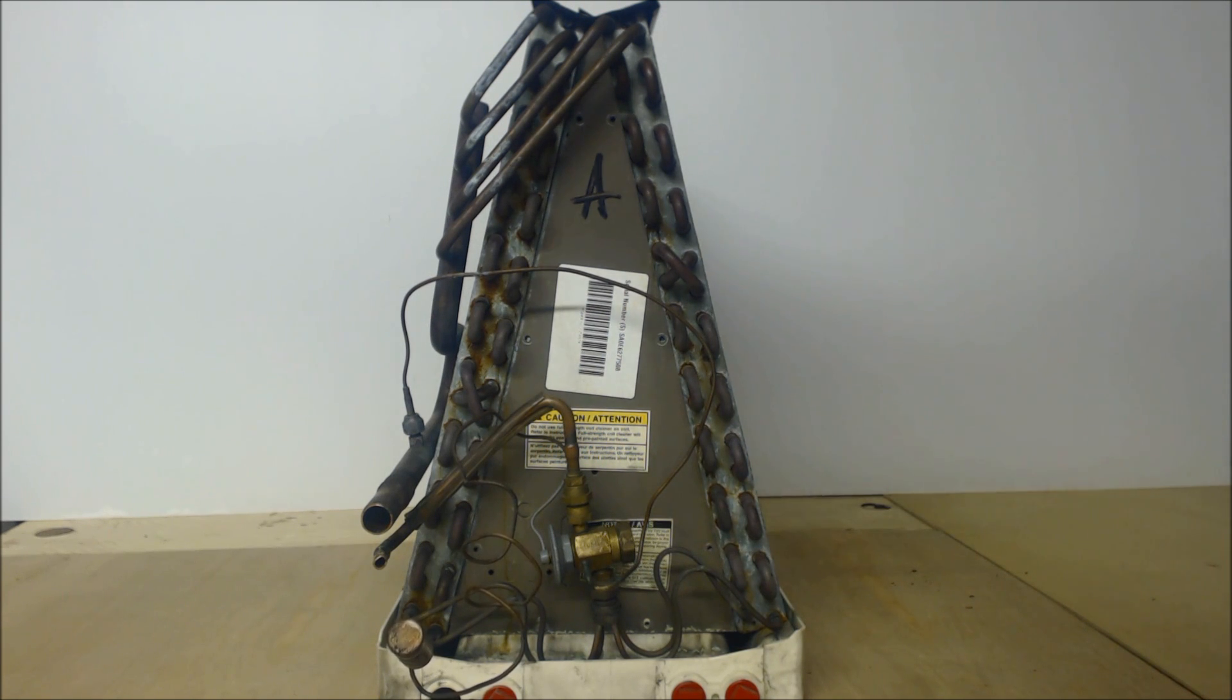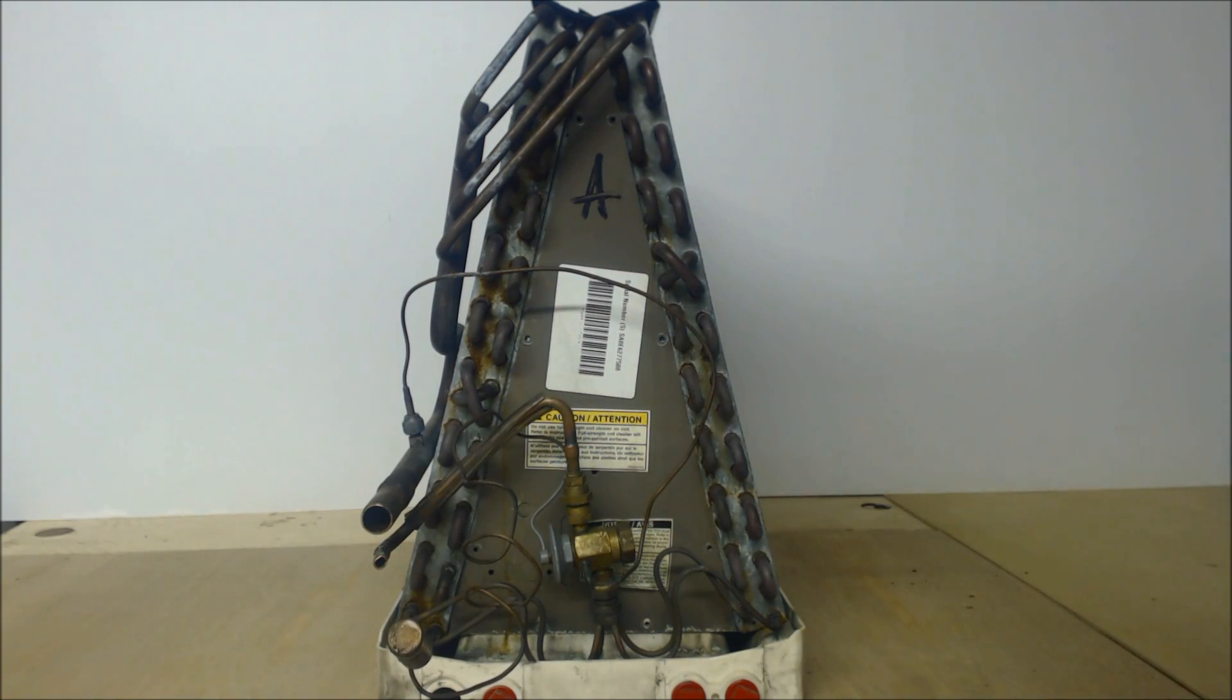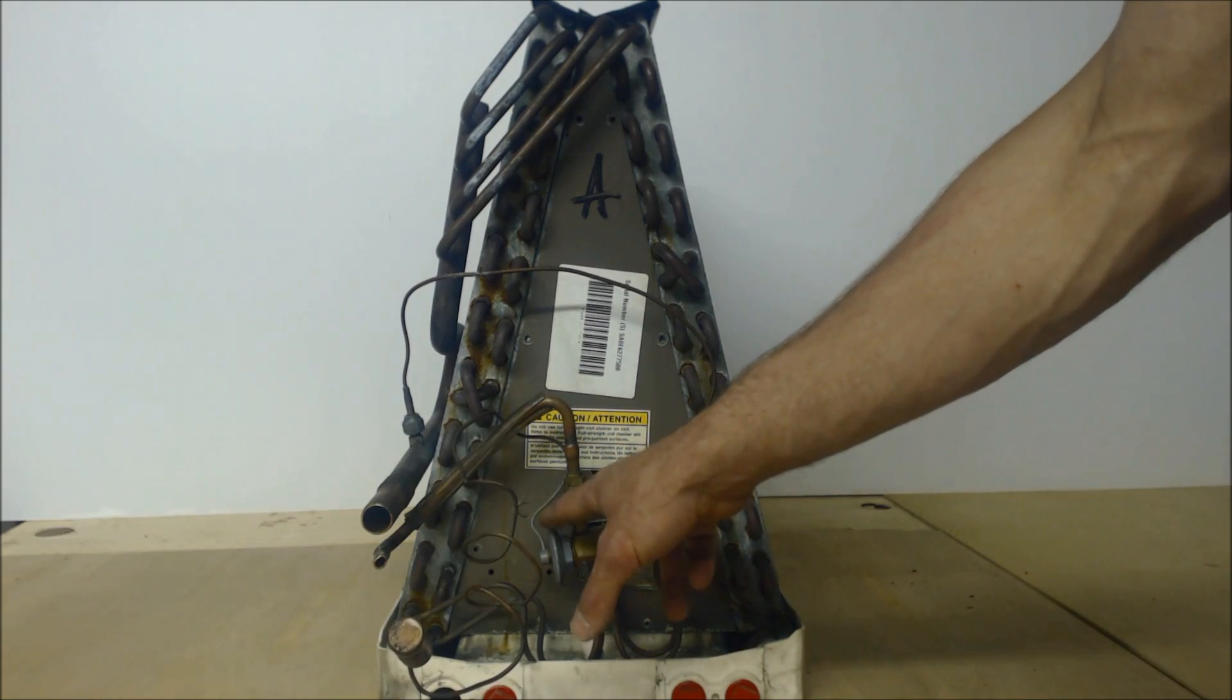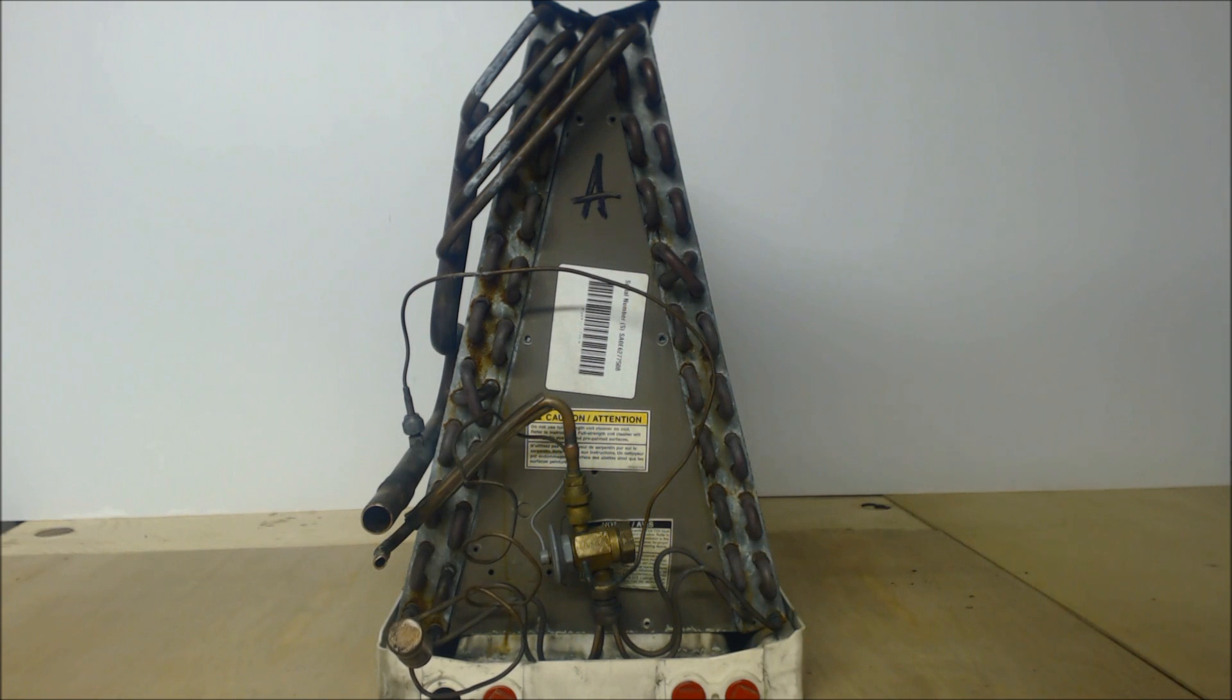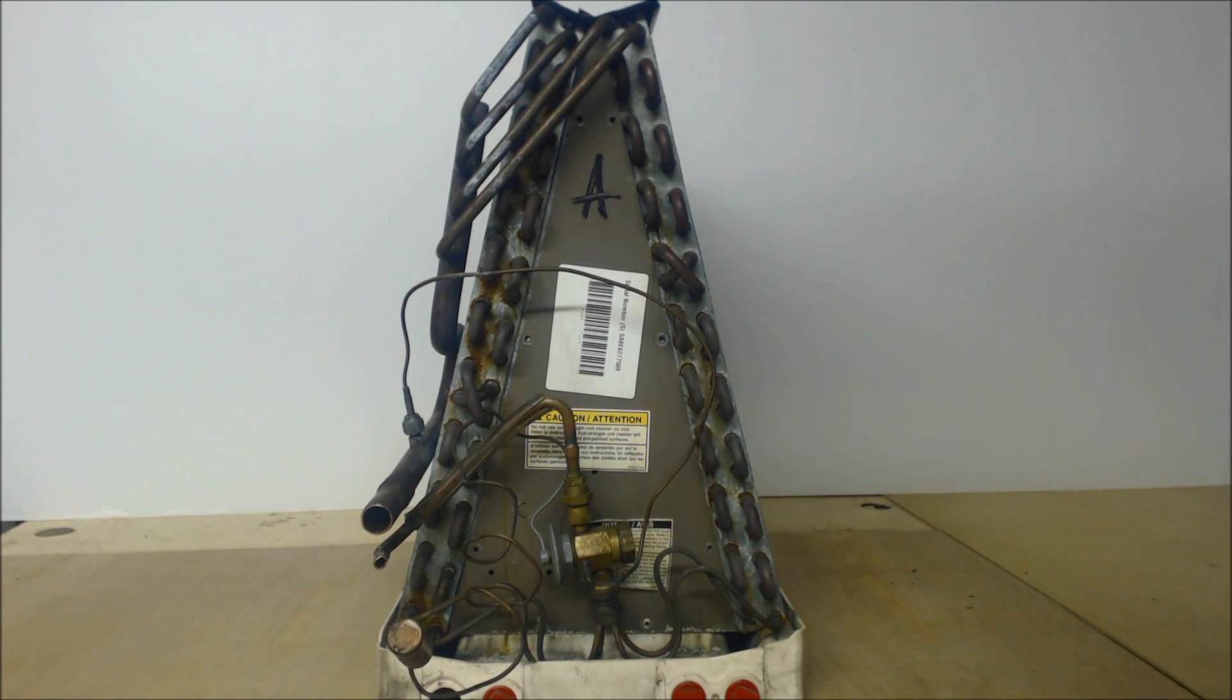If you had a furnace that was larger with a 060 blower (60,000 BTUs - that's 12,000 BTUs per ton), and this was still 3.5 ton capacity, you could kick down that CFM (cubic feet per minute) value to something closer to 3.5 tons.